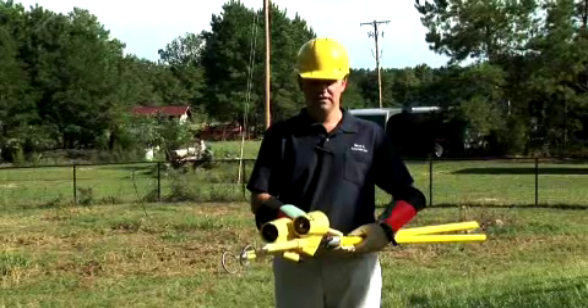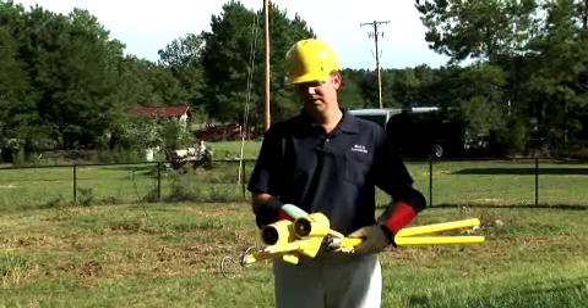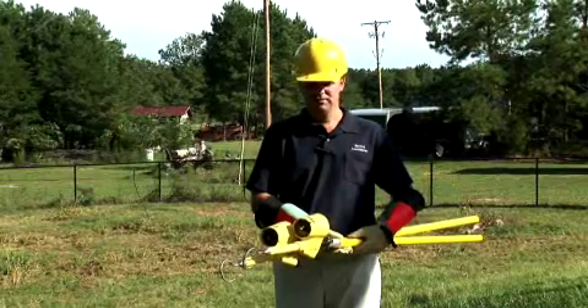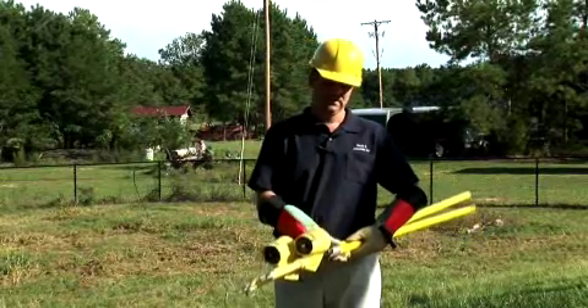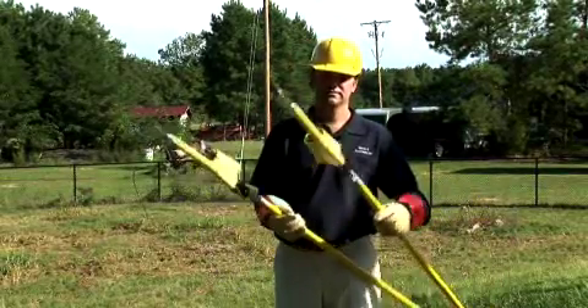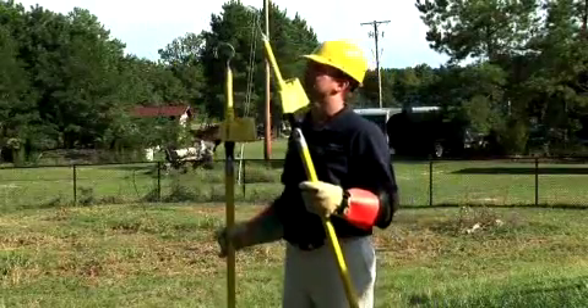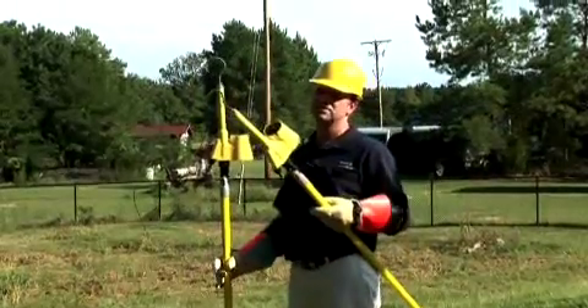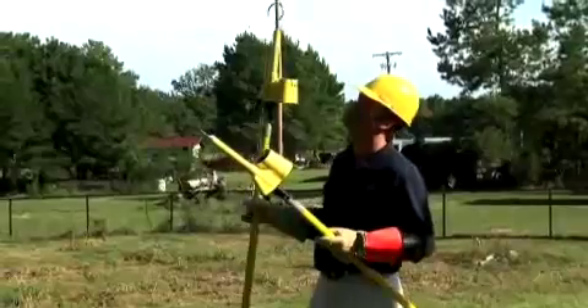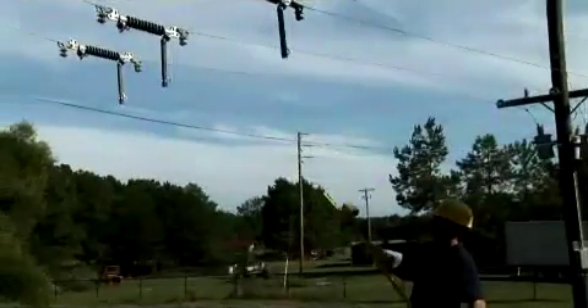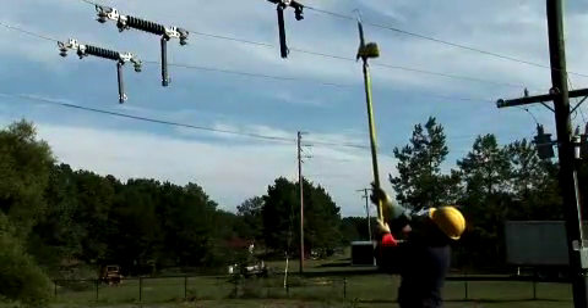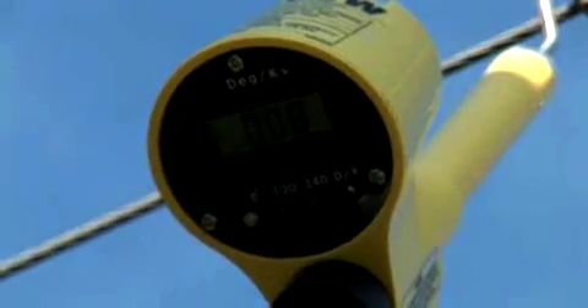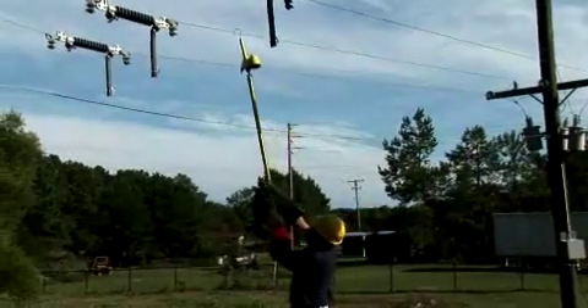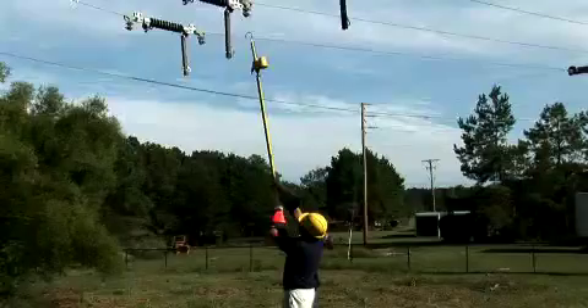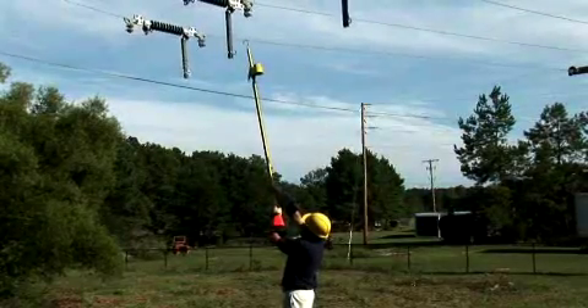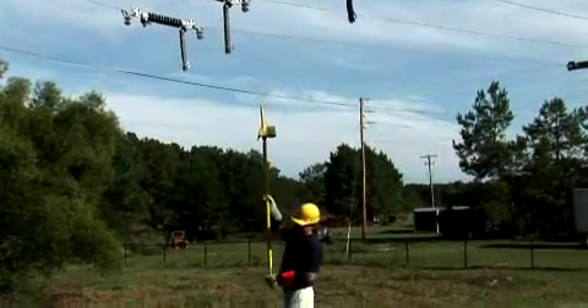All right, we have the PD800W meter, our wireless phasing meter, and I have the meter in the overhead position, and I'm going to demonstrate phasing with this meter. First, I want to check and see to make sure I have voltage on every phase before I phase with it. I'm going to take the meter probe and check every phase for voltage. I'm reading approximately 8 kV, 8 kV, and 8 kV on this side of the switch.